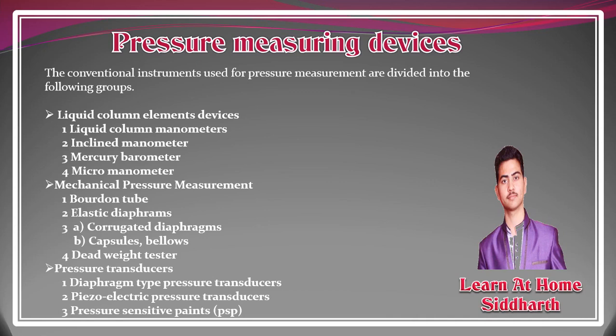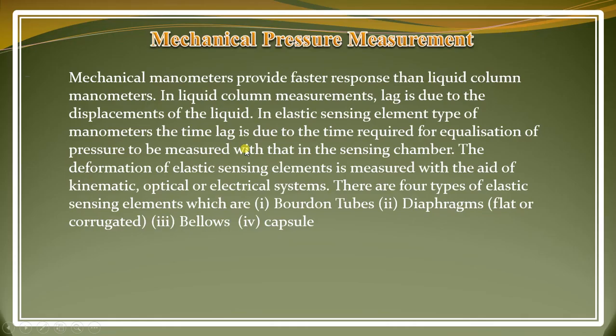In this session, we are going to talk about mechanical pressure measurement devices such as Bourdon tube, elastic diaphragm, corrugated diaphragms, capsules, bellows, or deadweight testers. So just move on to our lesson. First thing is, what is mechanical pressure measurement? Mechanical manometers provide faster response than liquid column manometers. Why? Because, as we told you, in liquid column manometers there is a lag due to the displacement of the liquid. We can classify our mechanical pressure sensors like Bourdon tubes, diaphragm, bellows, or capsules. We are going to talk about all these 4 types in our lesson.